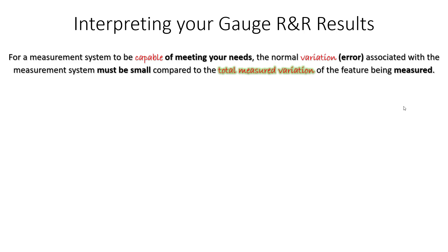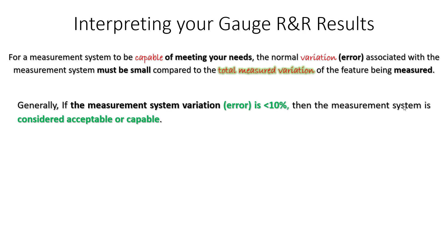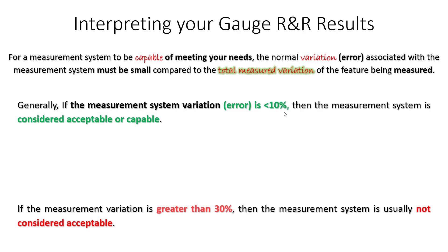Now let's talk about how to interpret your results. No matter which method you use, the interpretation is the same. In an ideal world, your measurement system variation should be small. Any calculation less than 10% is considered acceptable — no issues, you're good to go. That measurement system variation is small relative to your design tolerance or process variation. On the other end, if that percentage is greater than 30%, the gauge is not acceptable. You have too much measurement system variation and you need to address it.